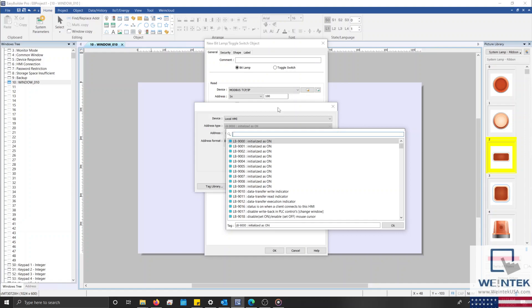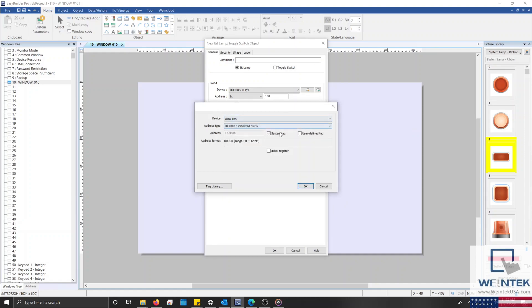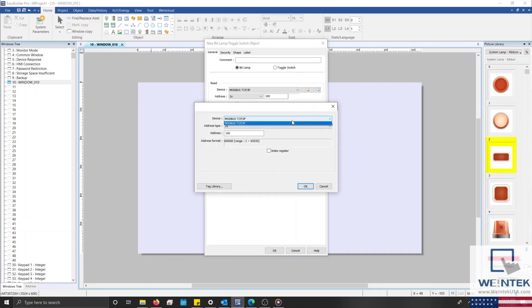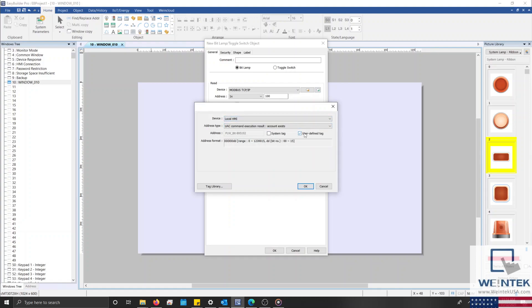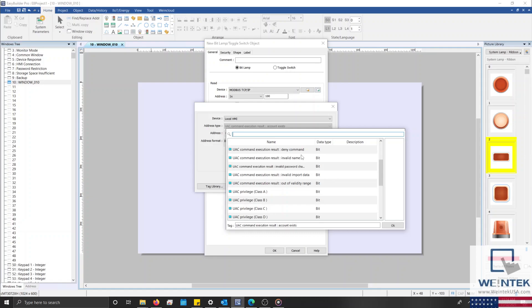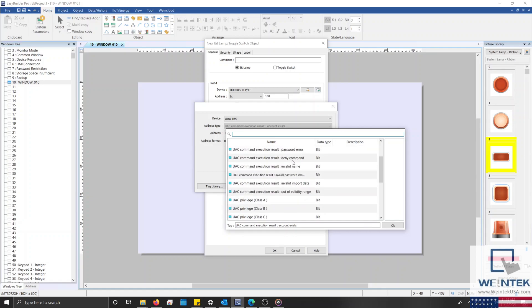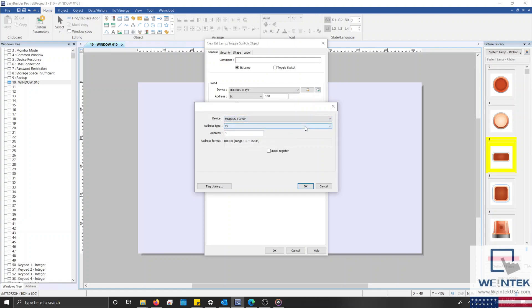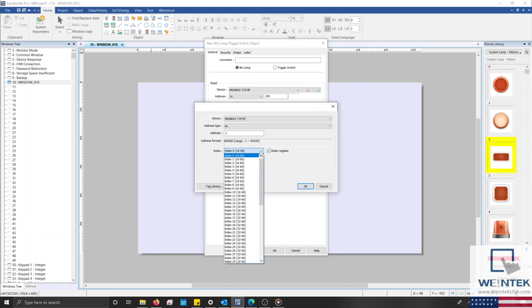User-defined tags are configured within the Tag Library or by selecting the Add Tag button, which is a small button that depicts a tag with a green plus next to the Settings button. By default, certain user-defined tags have been configured for specific PLC registers, which is why the User-defined Tag checkbox is accessible when our local HMI is selected. However, had we configured a tag for our Modbus device by using the methods previously described, this checkbox would be available when our Modbus device is selected as well. To assign an Index Register to the address within this object, we'll need to enable our Index Register checkbox and select an Index Register from the drop-down list.